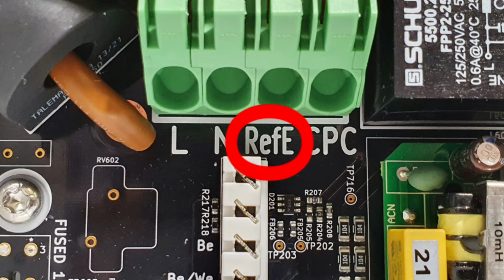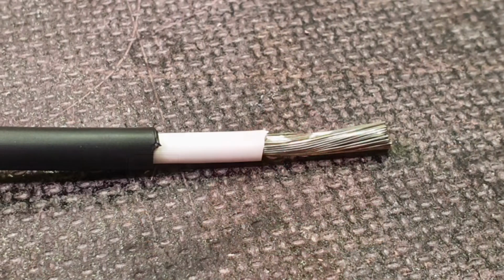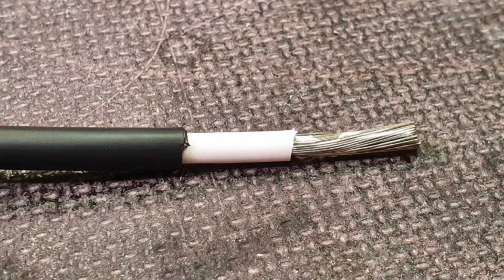So it's simply a matter of driving the earth reference electrode home near to where the charger is installed. Obviously, a measure of caution still needs to be taken when driving an electrode into the earth. And the longer the rod, the better. However, it can be achieved with a shorter rod, as long as you achieve a resistance of 600 ohms at 1 meter. As this connection is not an earth, an equipotential bond, a CPC or a functional earth as defined by BS 7671, Indra recommend connecting with either a 4mm or 6mm solar cable, which is generally black in colour.